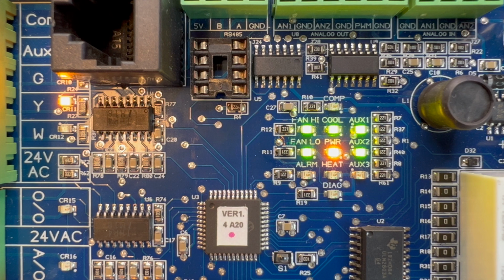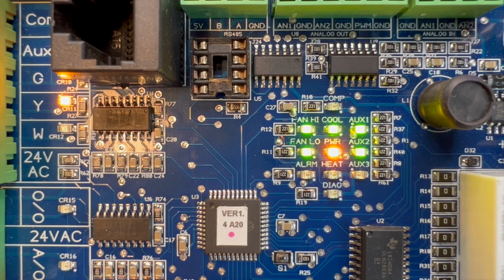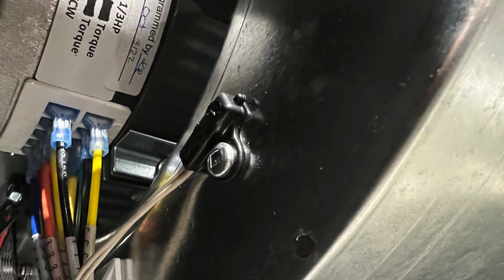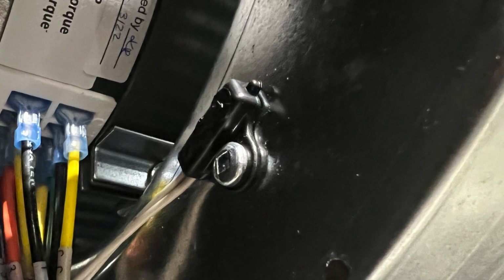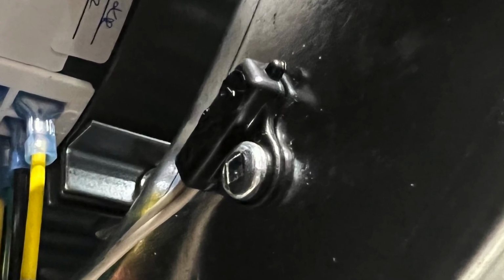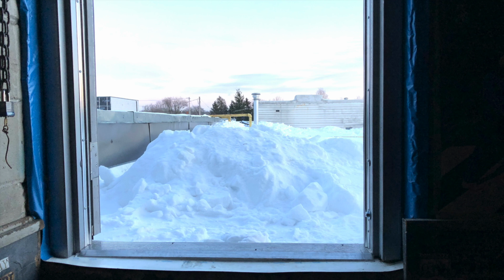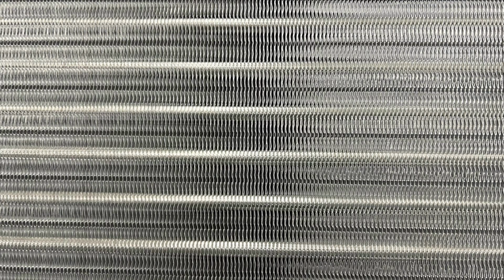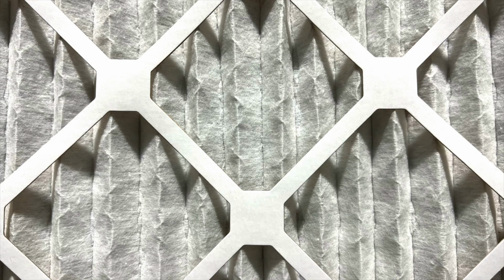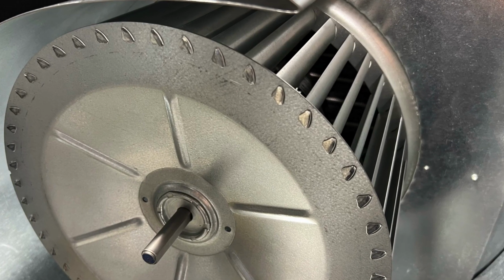4 flash, low discharge air temperature. This fault code indicates a temperature below 40 degrees Fahrenheit has occurred at the fan inlet. The unit will reset when that temperature goes above 55 degrees Fahrenheit. The 10K thermistor is located at or near the blower inlet. Possible causes of this lockout are cold air entering the return air of the unit, or restricted airflow due to dirty coils or dirty air filters, or even poor blower performance.